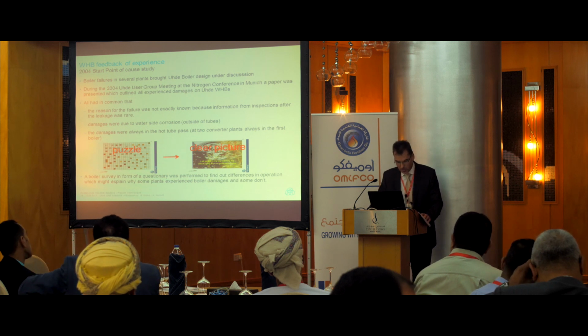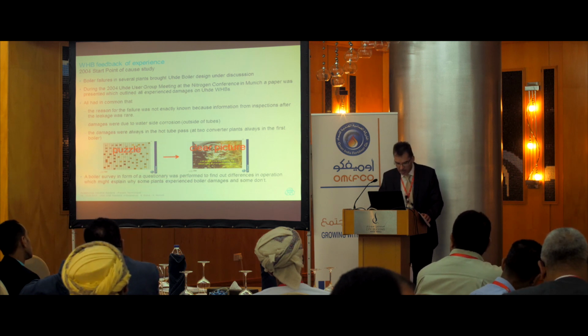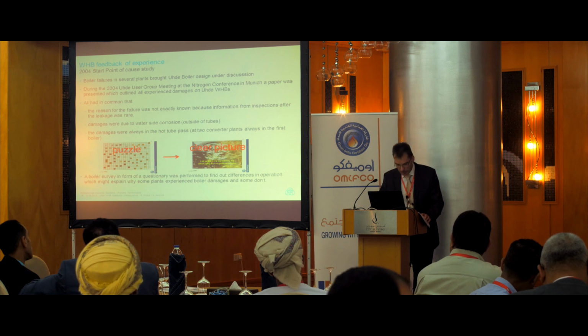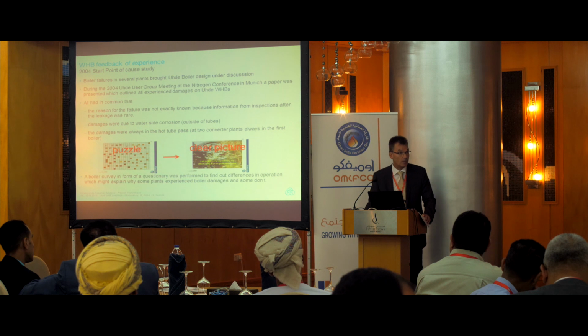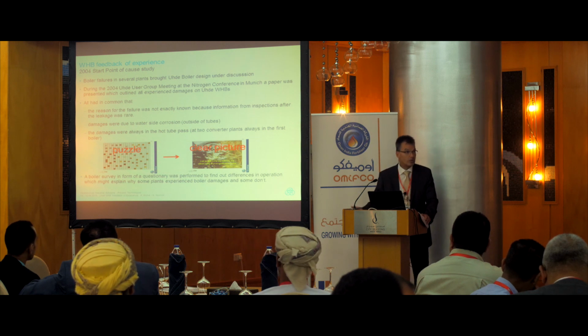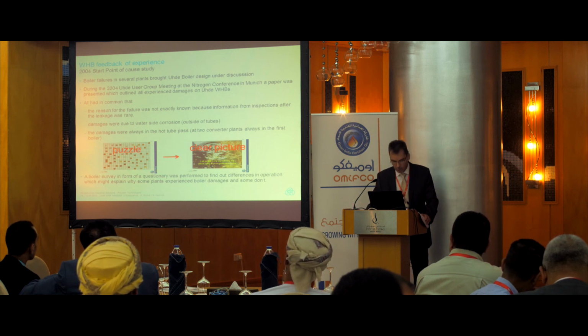Due to lack of information, a lot of speculations came up. Is it high heat flux at the tubes? Is it steam blanketing at the tubes? Is it insufficient steam exit of the waste heat boiler? Is the water quality bad? Or is it even a lack of intermittent blowdown? All this was discussed vehemently.